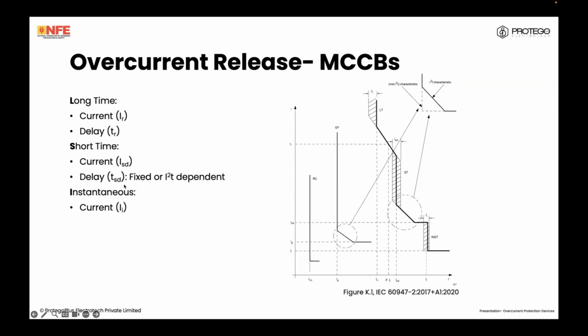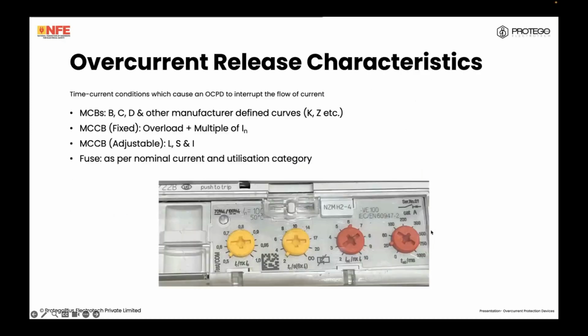Some circuit breakers also have the instantaneous setting, which means that if, say, you set instantaneous at 14 times IN, it will directly trip without any time delay, because that current is so high that it could damage the circuit. So it will instantaneously trip without waiting. So if I go back, see here, I've set an IR, I've set a TR, I've set an ISD and a TSD. This circuit breaker does not have an instantaneous value. But this is a very practical approach to this particular subject.